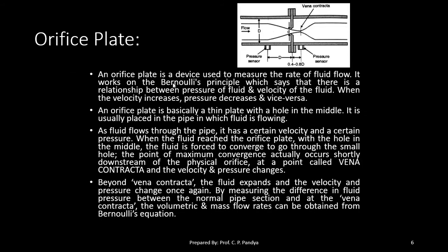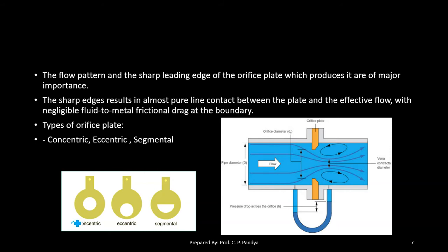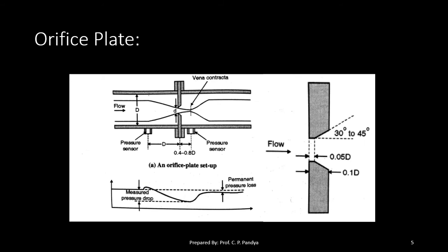The orifice plate comes in different shapes: concentric, eccentric, and segmental. Concentric means the center of the orifice plate coincides with the center of the pipe. Eccentric means the center of the orifice hole is displaced from the center of the pipe. Segmental means a half portion of the pipe is covered by the orifice plate. The orifice plate measures fluid flow and operates on the principle of Bernoulli's theorem.